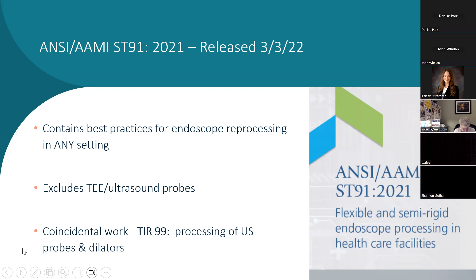So this contains best practices for endoscope processing in any setting, where SGNA and ASGE especially spoke predominantly to the GI realm. This is for flexible endoscopes of any kind used or processed in any setting. It does not speak to TEE probes or ultrasound probes, but the same work group that wrote ST91, as we were finishing the work on this, realized that there was a paucity of information available when it came to ultrasound probes and dilators. So just a couple weeks ago, TIR 99, Technical Information Report 99, was published that speaks directly to those. A TIR is not a standard. It could eventually become a standard, but it helps to provide timely guidance on addressing ultrasound probes and dilators.